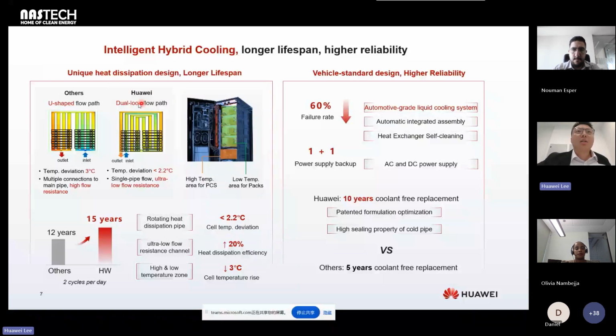Okay, the next one is a hybrid cooling system introduced. First is our battery, and the PCS is separate in four separate areas. The PCS is the power modules. During charging and discharging, the PCS integrates the IGBT. The IGBT turns on and off more than 1,000 times per second, so it generates a lot of heat. So our simple design can reduce the cell temperature by 3 degrees.